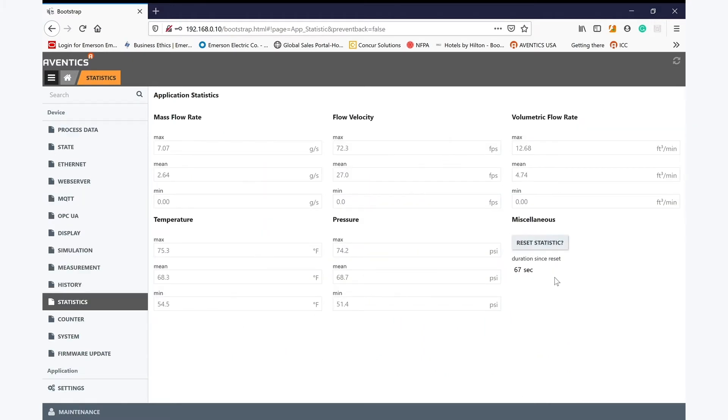And we can also use the web server to capture information and really start to understand the nominal air usage over a machine cycle. This information is also captured in the statistical data, again helping understand our nominal air usage.